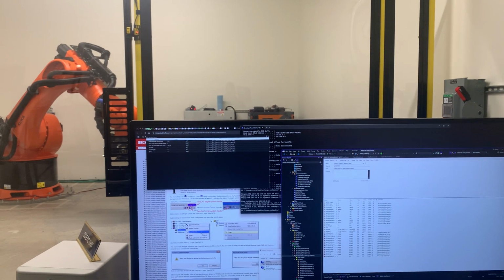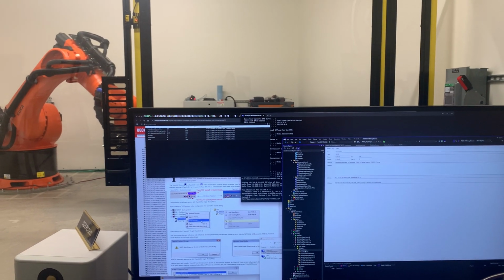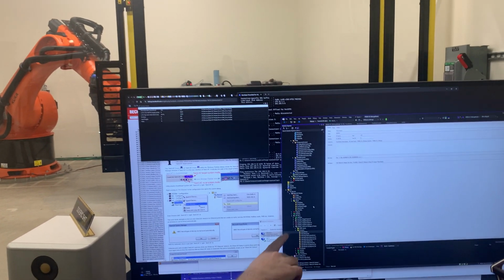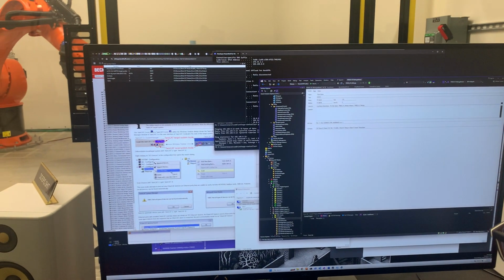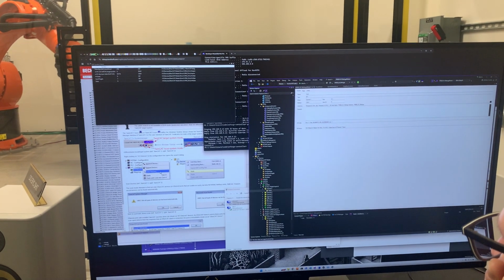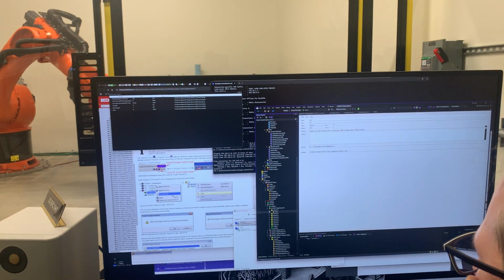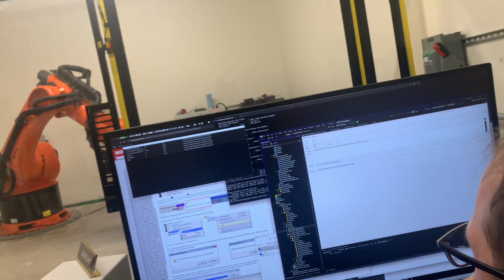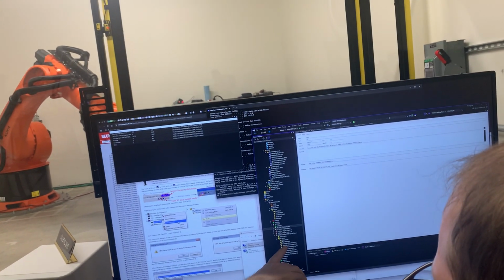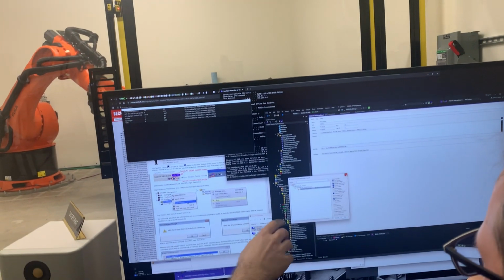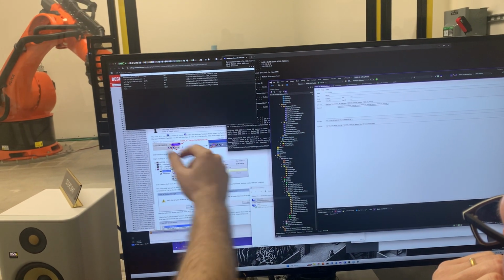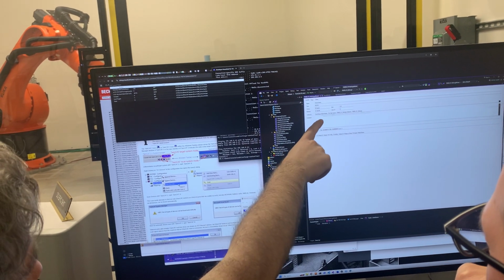If you click on them, you can add to that specifically for the bridge. Something like the digital input, the EL1018 digital input: if you click on that, that's a static digital input module. If you click down, there are 8 channels of digital inputs, and you can map those to different bits. Essentially, if you double click on a robot state, anything under the IO, you can see this is linked to that global variable from robot states.